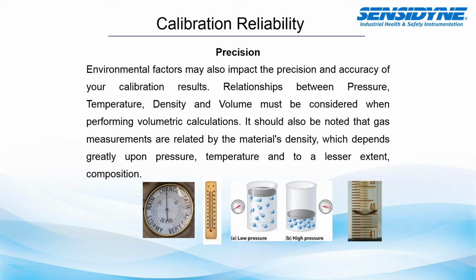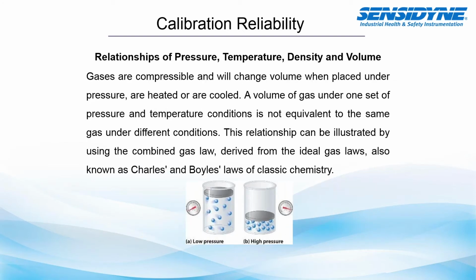Relationships between pressure, temperature, density, and volume must be considered and understood when performing volumetric calculations. It should also be noted that gas measurements are related by the material's density, which depends greatly upon pressure, temperature, and to a lesser extent, the composition of the material. Now, the relationship of pressure and temperature and density and volume as it relates to calibration. Gases are inherently compressible and will change volume when placed under pressure, if they're heated or if they're cooled. A volume of gas under one set of pressure and temperature conditions is not equivalent to the same gas under different conditions. Now, this relationship can be illustrated by using the combined gas law, which is derived from the ideal gas laws, also known as Charles and Boyle's laws of classic chemistry.